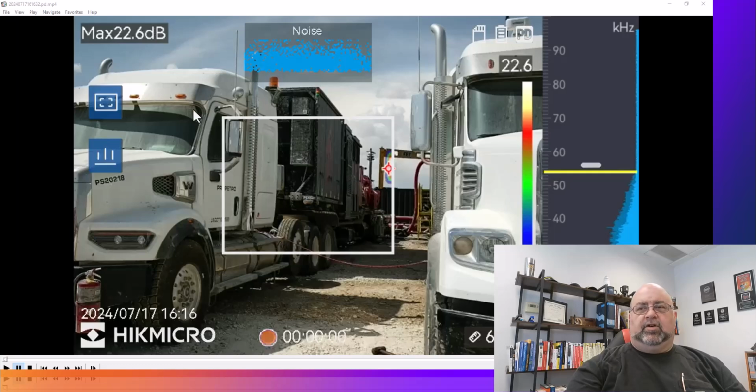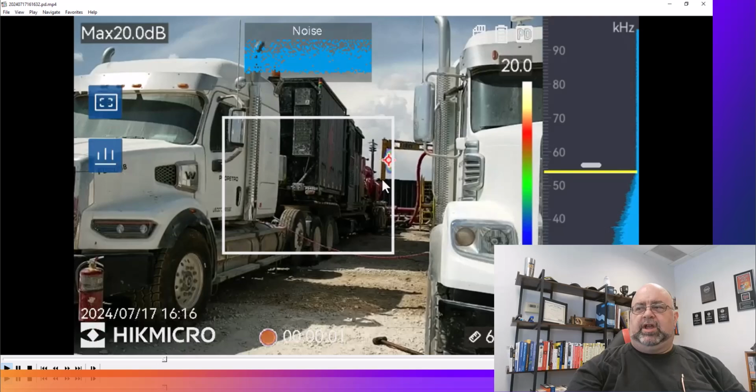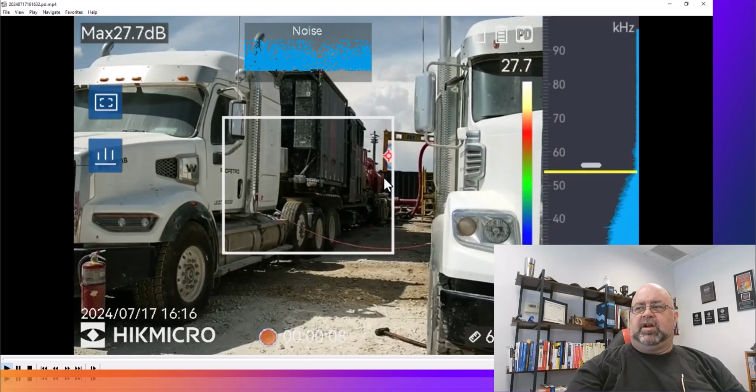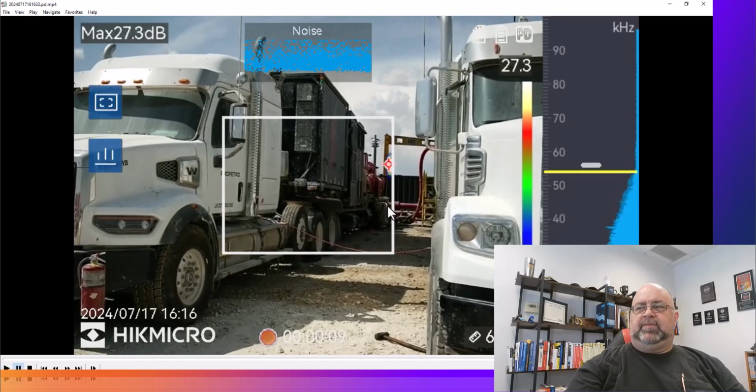Okay, so last but not least, let's take a look and listen to what it was seeing. And you'll also see it's bouncing around the detection point because of the types of things that are set up. Now, some of it's down because the pipes aren't popping, but that's basically what we had been looking at: transformer, and then drives, and then motors and pumps in the back while we were taking a look at these.